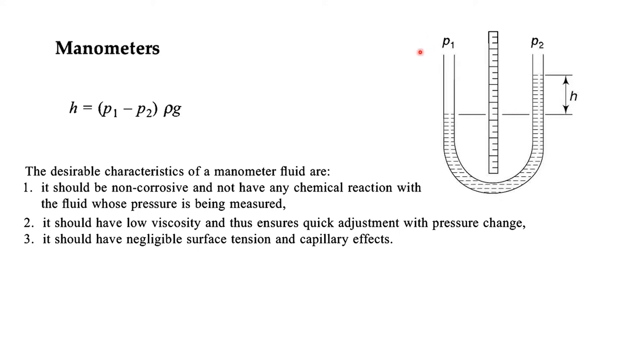Suppose P1 is the pressure we want to measure and P2 is exposed to the atmosphere. If P1 is high, it pushes the manometric fluid downwards and there is some difference between the two levels. Suppose this is equal to h; then h can be related with the pressure difference by the equation P1 = P2 + ρgh. Since P2 is usually the atmospheric pressure, P1 can be calculated from this equation.